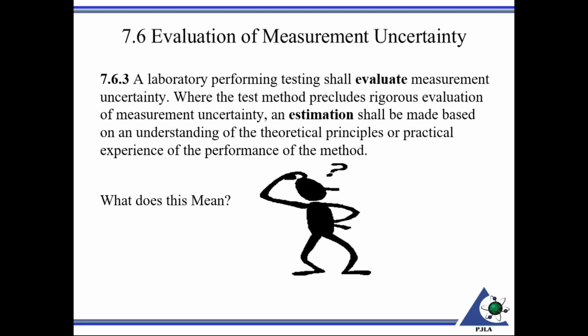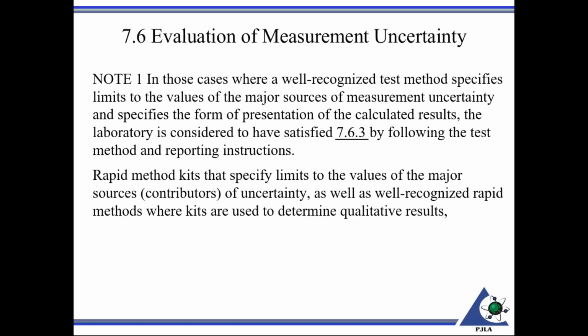All right, 7.6.3. There are only 3 clauses here under section 7.6. A laboratory performing testing shall evaluate measurement uncertainty. Where the test method precludes rigorous evaluation of measurement uncertainty, an estimation shall be made based on an understanding of the theoretical principles or practical experience of the performance of the methods. So what are we talking about here? This comes right out of the standard. And these are notes. In 17025, notes are just, I like to refer to them as FYI or supporting information. They're not requirements.